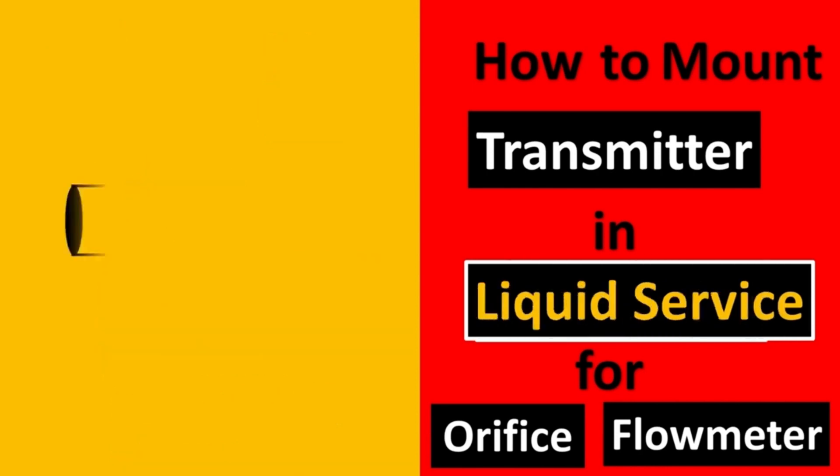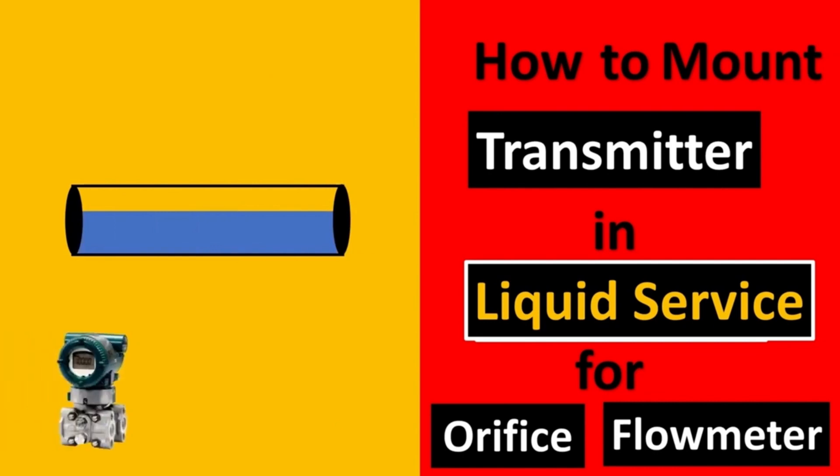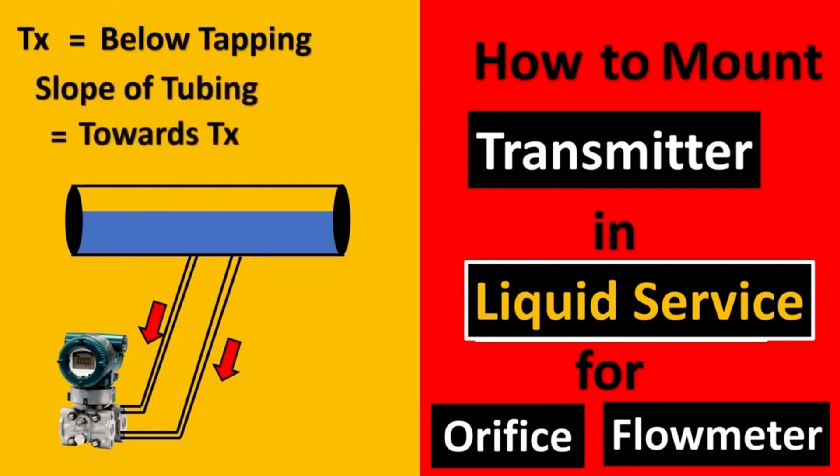Now the next question is what do you do in liquid services? In liquid services, the transmitter would be below the tapping and the slope will always be towards the transmitter and not towards the pipe. Why? Because you want the liquid to be trapped here, and if there is any gas which is lighter, it will always stay up and never come to your transmitter. Thus the gas would not get trapped inside your impulse lines.